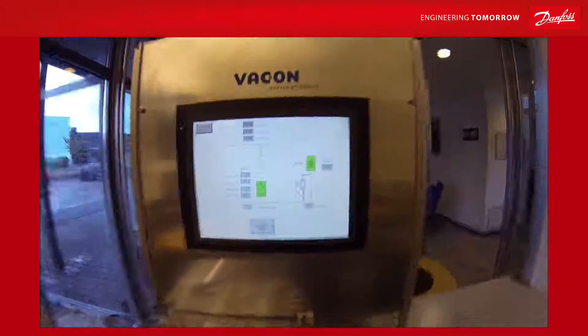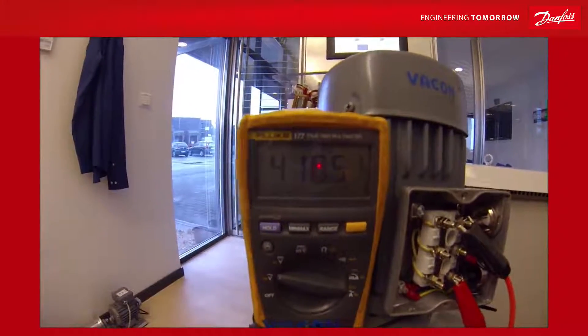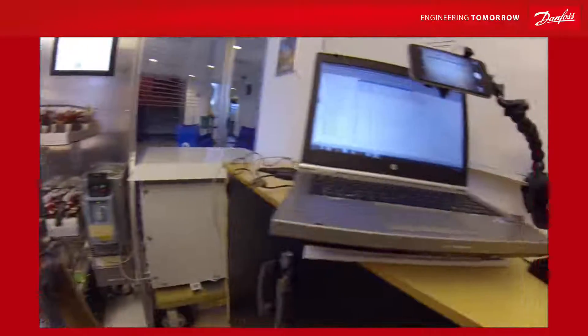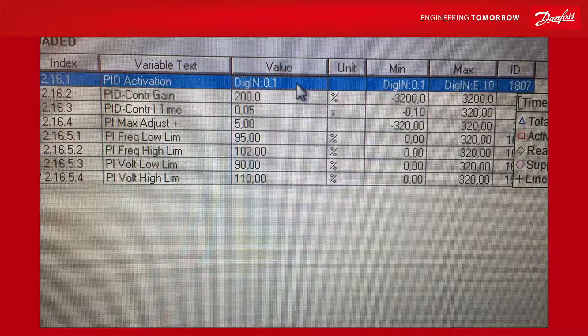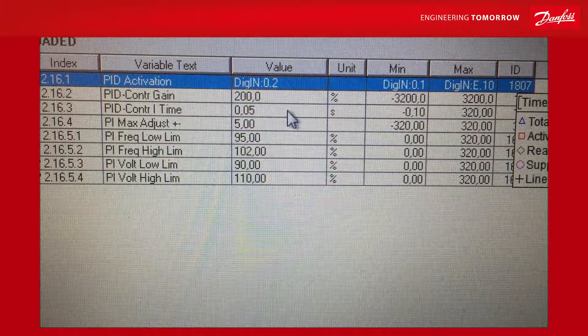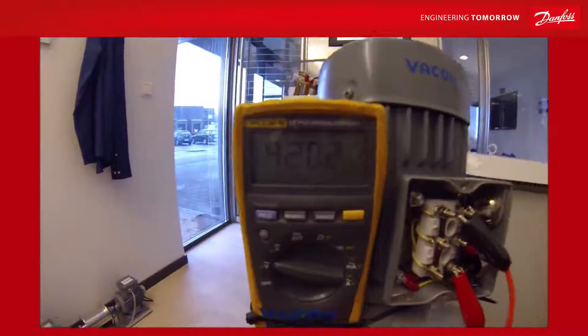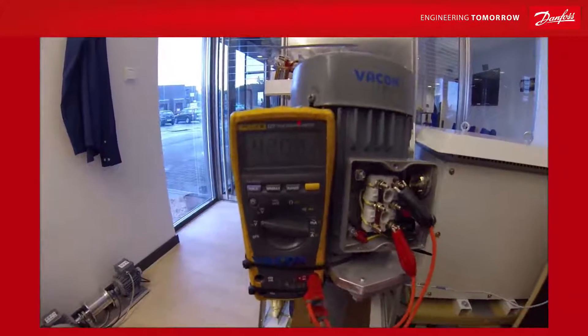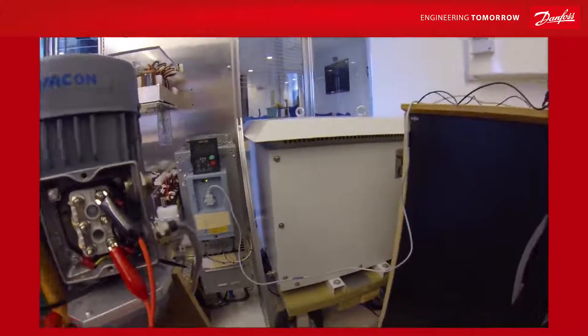Now we have the grid powering a consumer. If we look at the voltage, it is 418.5 — we asked for 420. Let's see what happens when we activate the PID regulator. The consumer is now adjusted to exactly 420 volts. The PID regulator acts on the grid voltage and adjusts accordingly, so the losses across all our transformers and filters are now compensated.